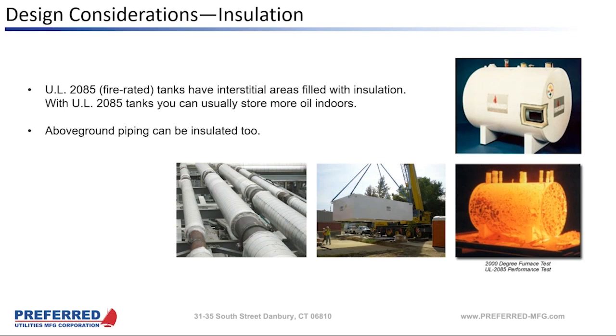One of the things I would definitely recommend when we're talking about insulating piping, I see a lot of designs where maybe you have a certain amount of fuel stored in interior or below ground or something like that. And usually the discussion becomes insulating and heat tracing the containment piping. And I think that's a really good option as long as we understand what the goal is with insulating, and even with insulating and heat tracing piping.